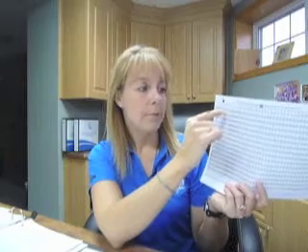Here you can write wax temp, safe range between whatever is suggested for that wax bath. Some of them are low temperature paraffin baths and some of them aren't. So just check in the manual to see what the operating safe range is for that wax bath, and write it on your form so that when you're checking it off on the days that you use the wax bath, you're indicating that you've checked that the wax bath is in the safe temperature operating range.